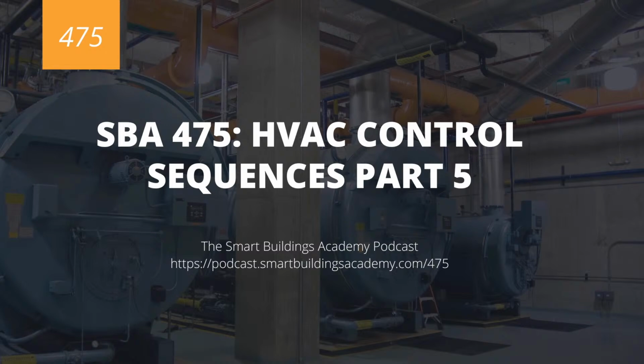So unison control is where both boilers, or all of the boilers if there's even more than two, are run in unison. Now, the beauty of this is that this really helps you to not have to worry about bringing on a boiler and potentially having to have that boiler run in low fire before it can be added to the loop, because you don't want to be running really cold water through a boiler, or introducing cold water into a loop, or introducing really hot water into a boiler and sweating. There's all sorts of issues that you can have with a boiler. So unison control largely avoids that.